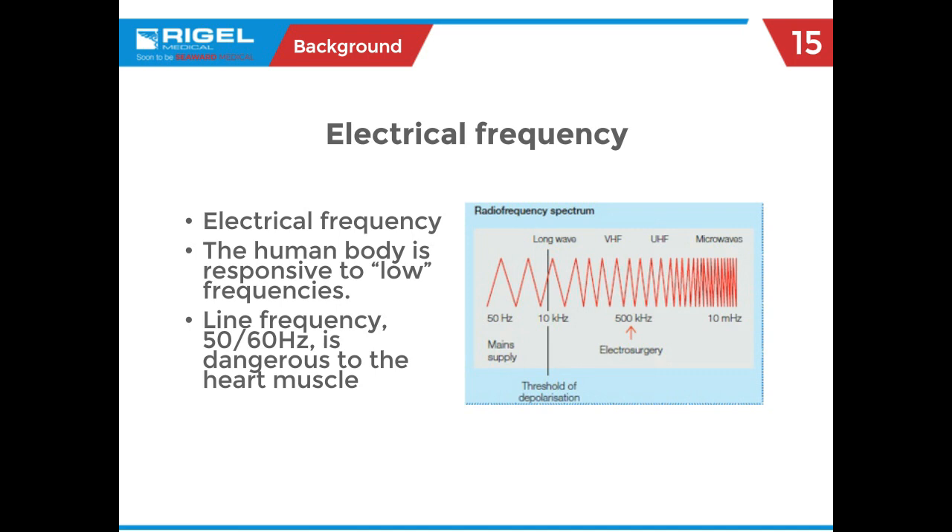The frequency is dangerous at low levels. When you start to look at the frequency spectrum, you'll get up to 100, 120, or 200 hertz — that's where physical therapists with their electrical stim machines exercise muscles. Continuing up the spectrum, around 400–450 kilohertz and above you'll run into ESU generators — most operate between 450–500 kilohertz today, while newer lower-power units operate up at the one megahertz range.